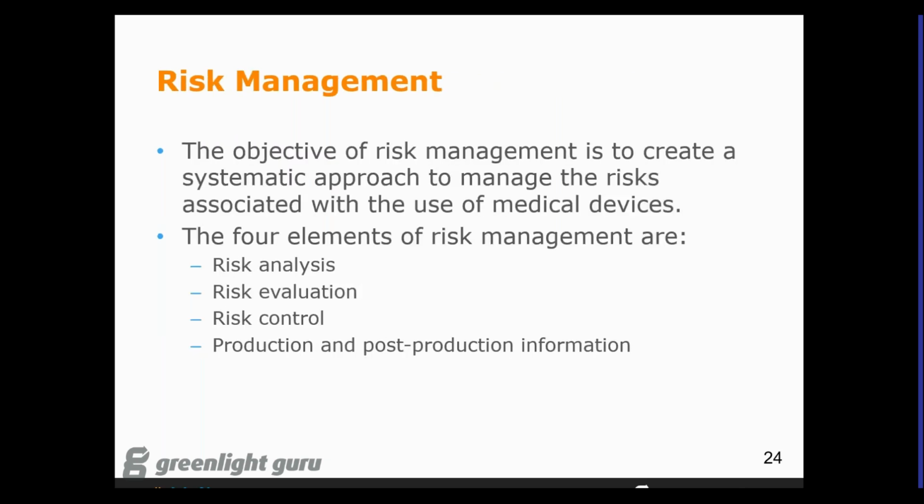So mention just there the risk management. I wanted to take a minute here to cover that. So here we want to make sure that the 4 elements of a risk management system: analysis, evaluation, control, and your production and post production feedback to continue to evolve that.